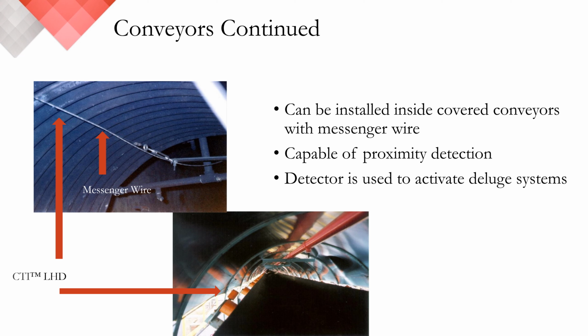In some cases, the conveyors are covered with metal hoods. In these areas, we can provide detection not only below in the area of the bearings and belts, but also above the materials being moved. In these areas, however, access to connection points to support the linear heat is limited. To accommodate long spans like this, you have the option of having the linear heat detector coupled with a messenger wire.